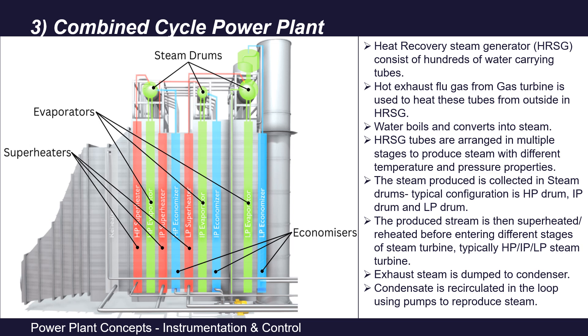Steam drums are located above the heated tubes. Steam rises up and is collected in the drums — the lower side is water and the upper side is steam. From the top of these drums, the steam is extracted and again superheated to make it suitable for steam turbine entry, so that it does not contain any water particles — otherwise it could cause corrosion of the turbine blades. This superheated steam is then passed to the steam turbine blades, the blades rotate, and electricity is produced.